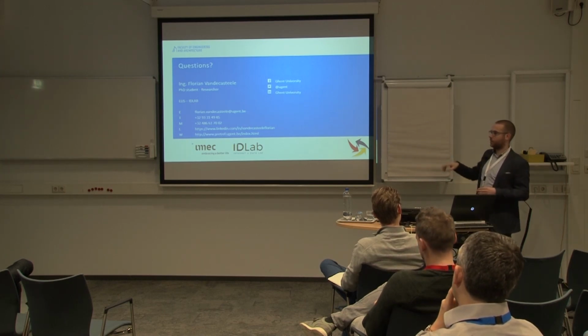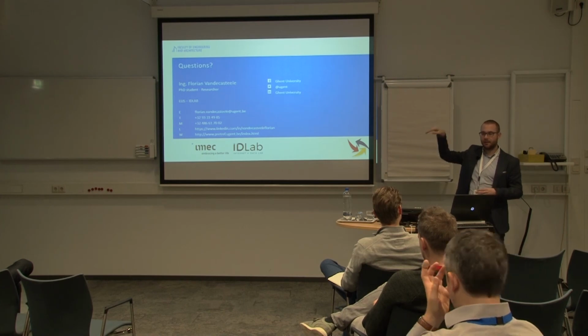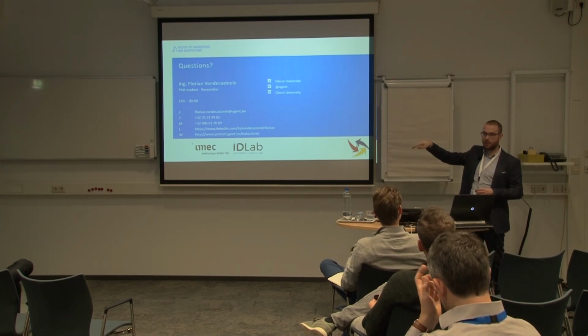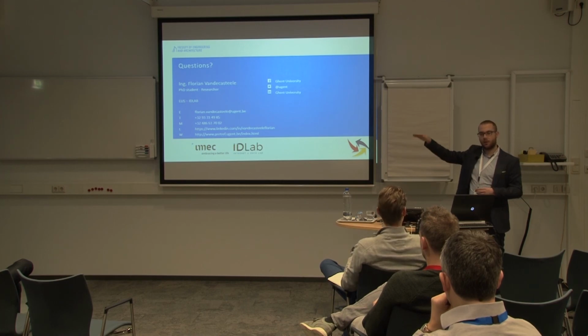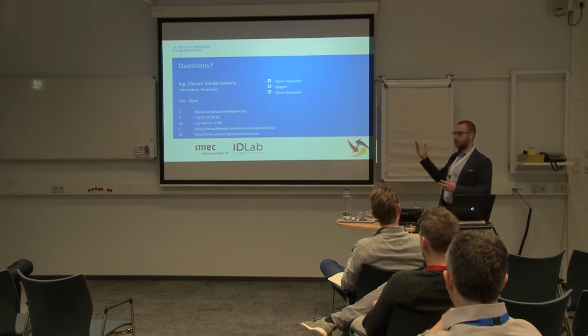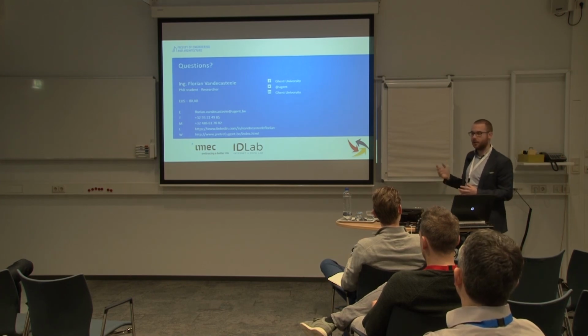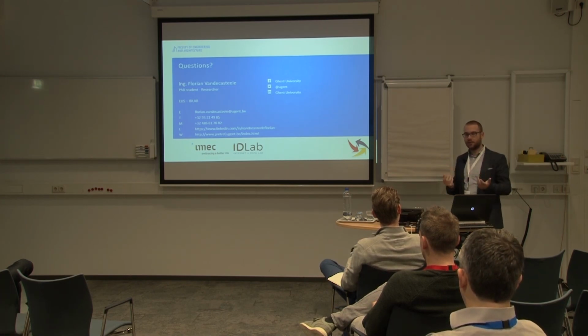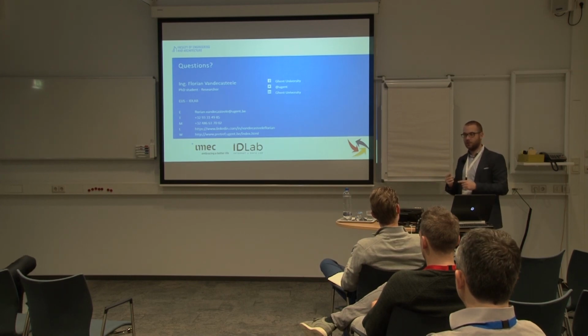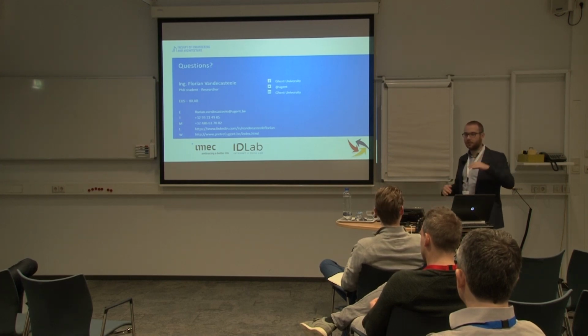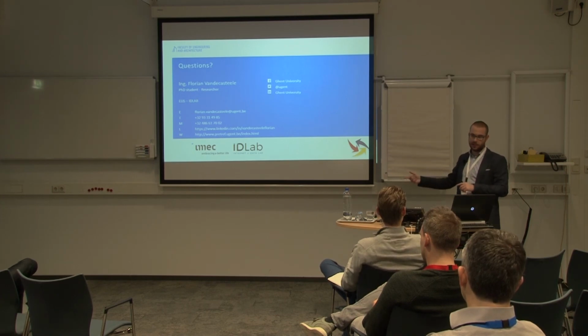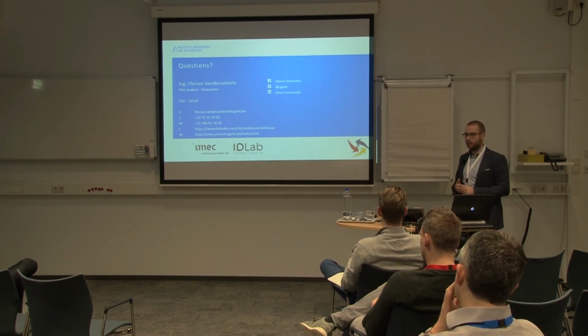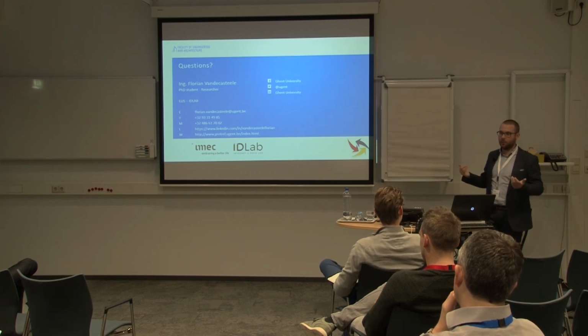But for instance, if there is a room that's burning, and you look through this camera, you are able to see what is going on. And we also use a combination of sensors. Maybe that wasn't quite clear in the slides. If a sensor fails, for instance in the tunnel experiments, there is always a check between the sensors. One sensor can't say 1 meter while the sensor in the neighborhood says 2 meters. That's not possible. Then we say this sensor is failing, but that's done automatically. But we are still aware that if the room is filled with smoke and the camera hangs on the ceiling, then we will have a problem.